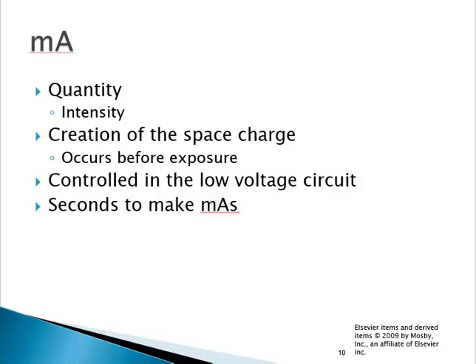Your MA is specifically responsible for heating the filament. It provides the electrons on the filament to heat it up and create the space charge, resulting in thermionic emissions. At this point you don't have x-ray exposure or tube current. The only things present in the prep stage are heating of the filament and rotating the anode — creation of a space charge and thermionic emissions — occurring before exposure.